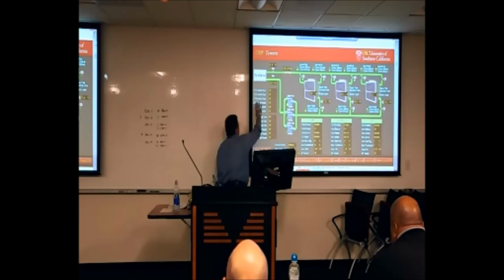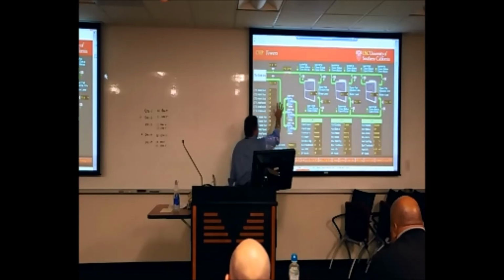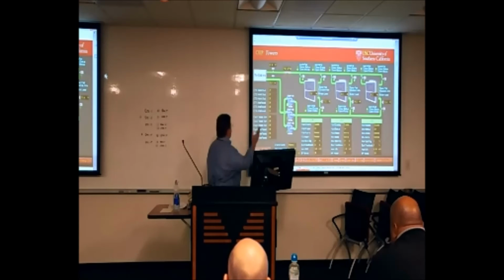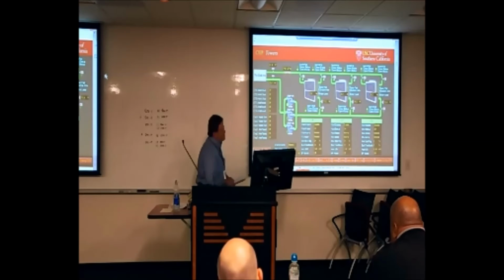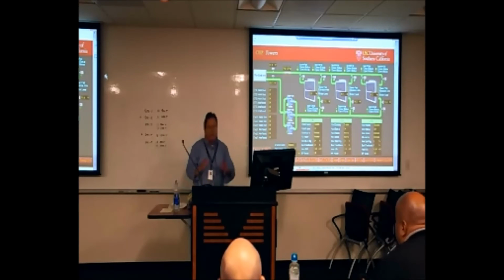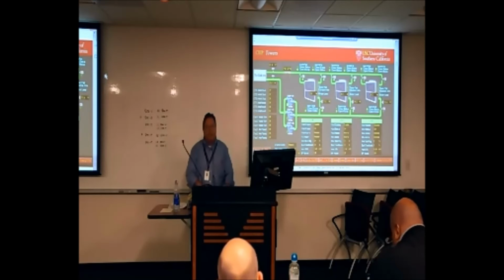And then similar to the pumps, we have a maintenance switch for each tower. So if a tower were down for any reason, activate the maintenance switch and the software will just skip that tower in the rotation sequence until that maintenance switch is cleared, and then it'll come back into the normal rotation. Any questions so far on points and just basic logic here?